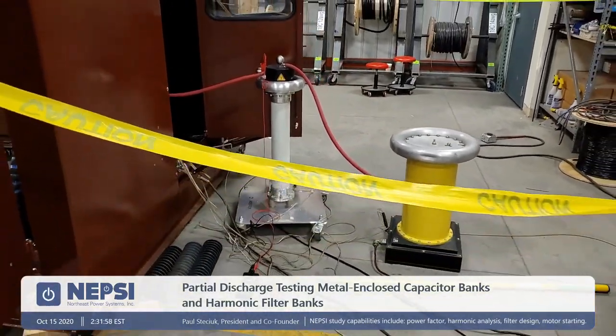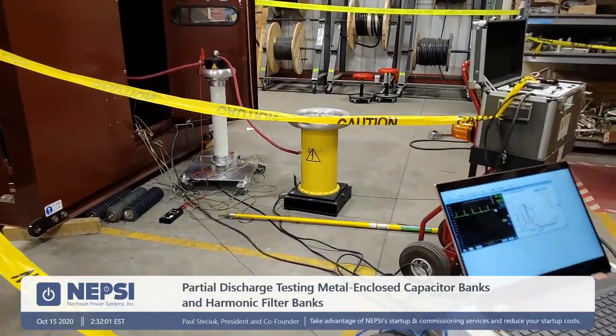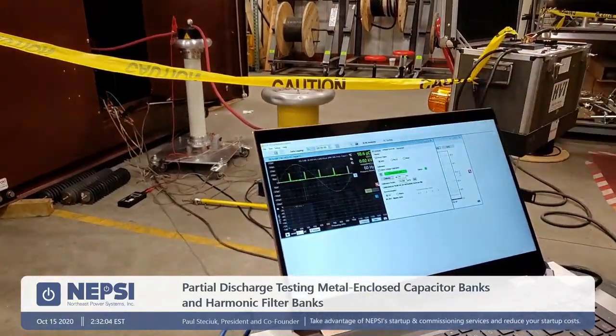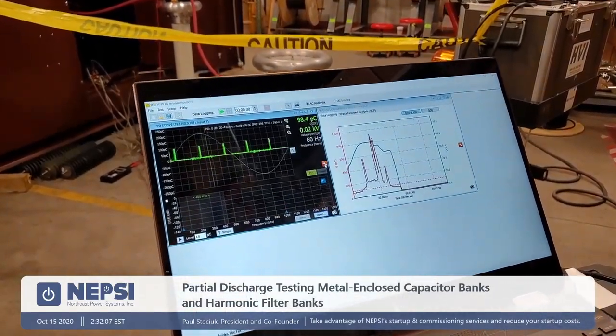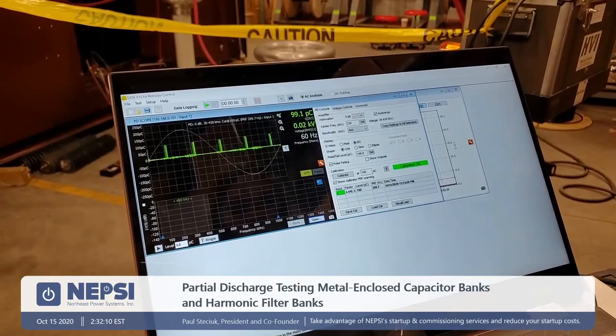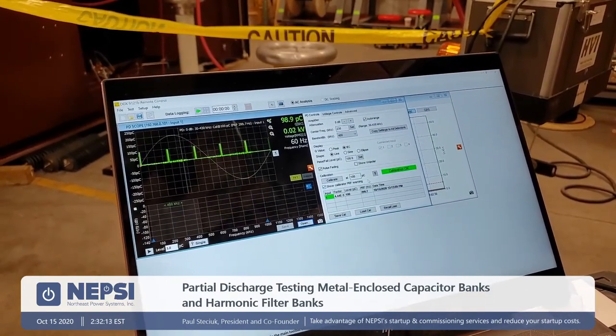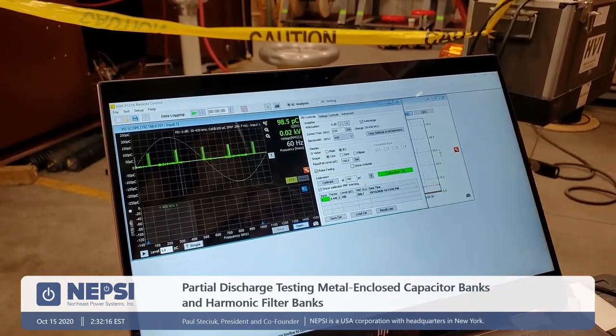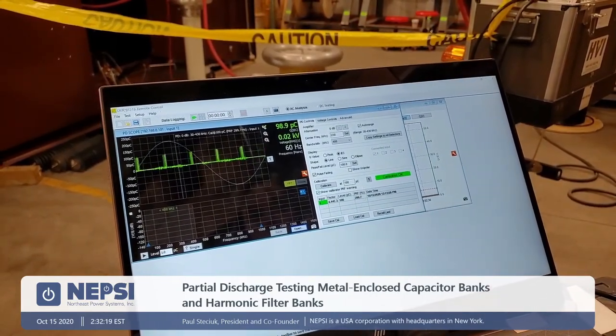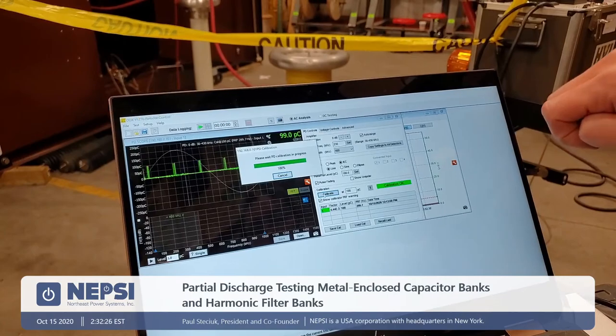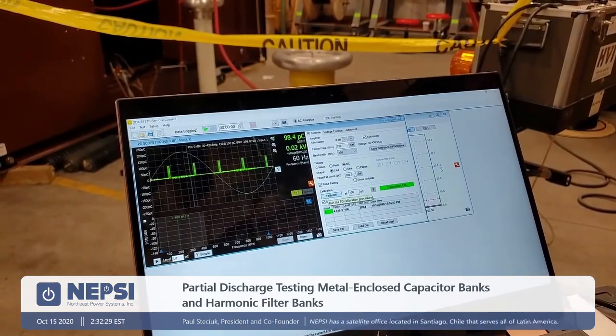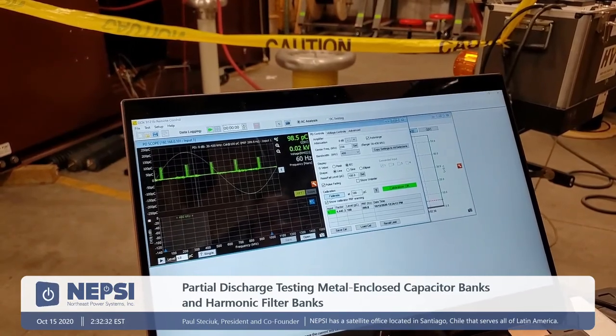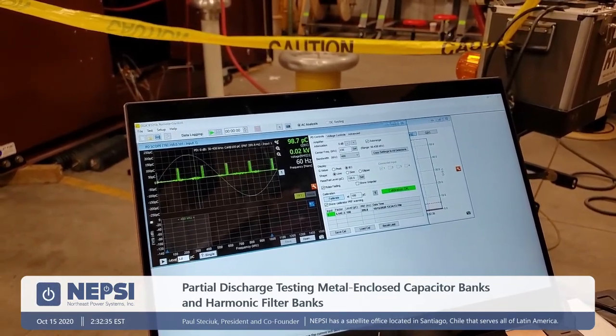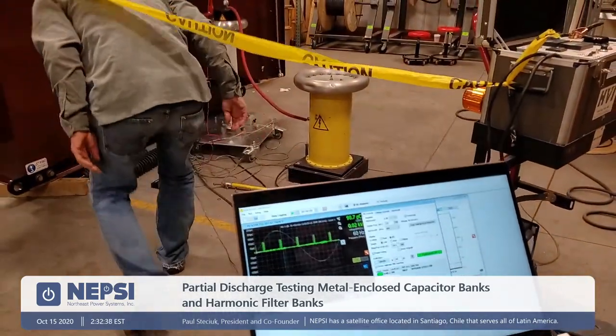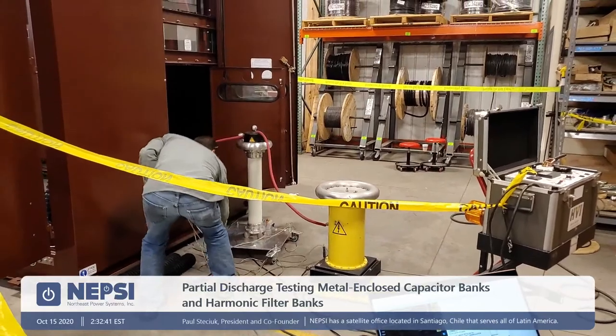So the calibration test instrument is hooked up. It's putting in a series of waveforms that is exactly equal to 100 picocoulombs. You can kind of see this in the waveform. So the measurement instrument is picking up that picocoulombs. And Jessica would then calibrate the instrument. I set the 100 picocoulombs here because that's what the calibration device is set to, and I just hit calibrate. And if you look here, it'll be about 100 picocoulombs because that's what we just calibrated it to. And then we also have to do the voltage as well, so that's next. And Peter will use the high voltage test set to calibrate it, and we calibrate it at 10 kV, just a lower level.